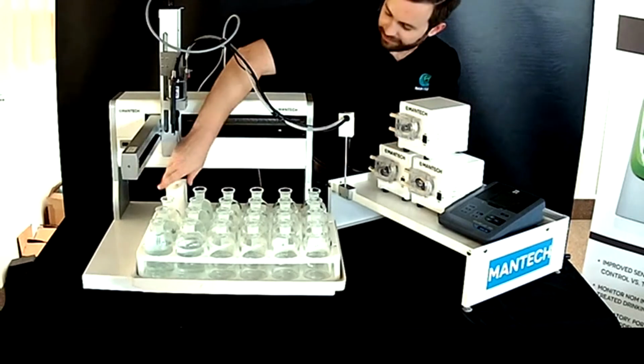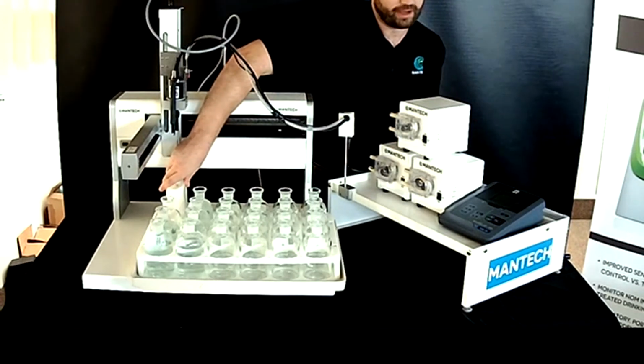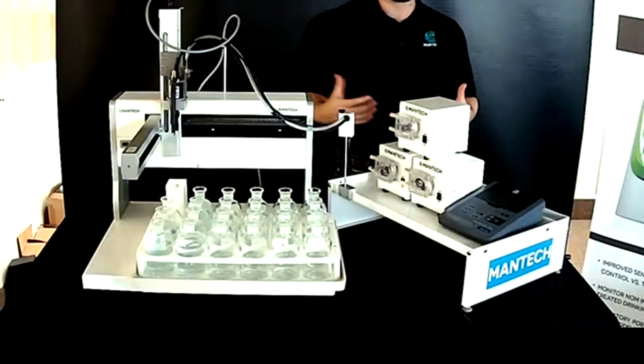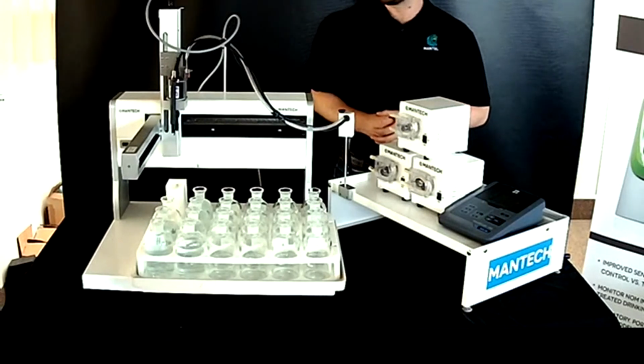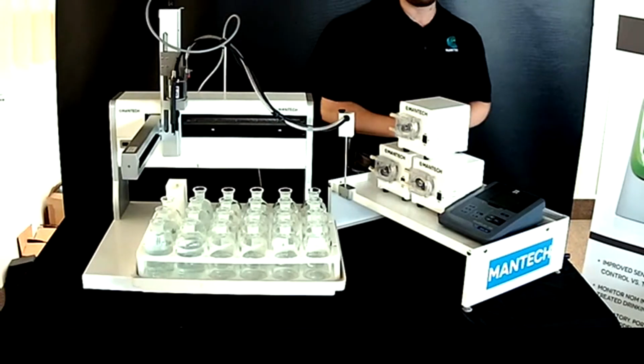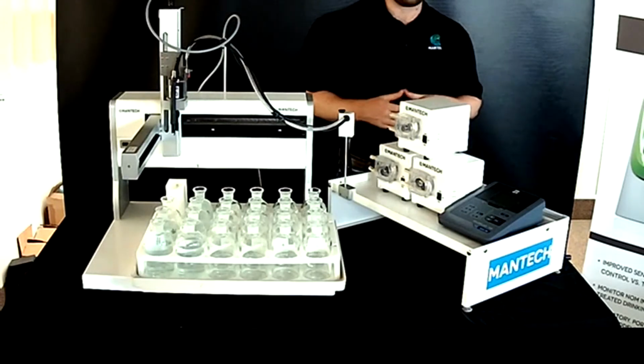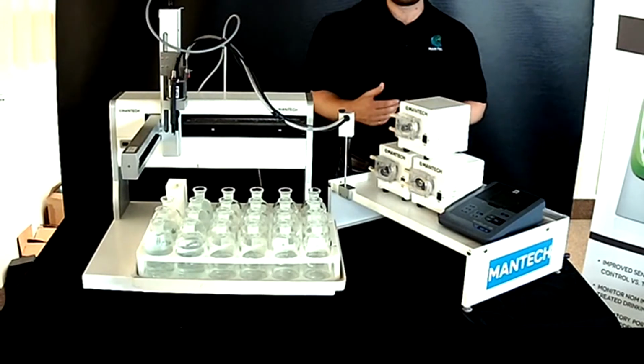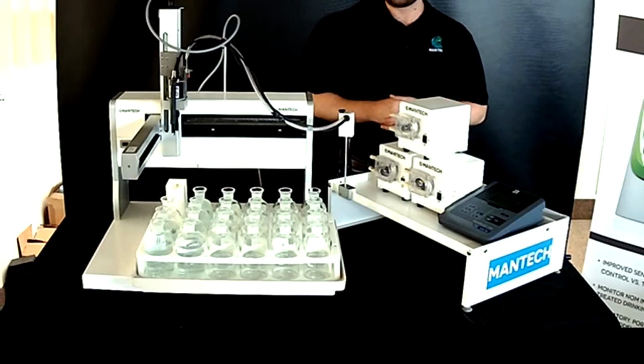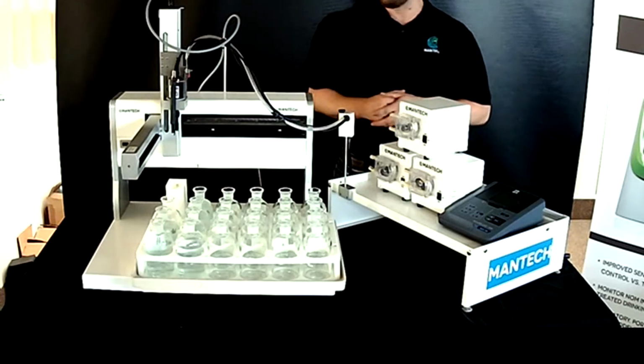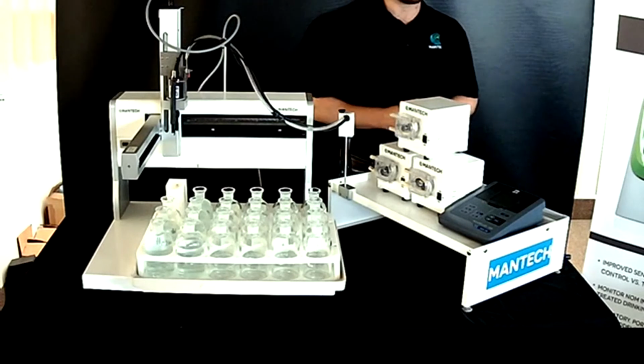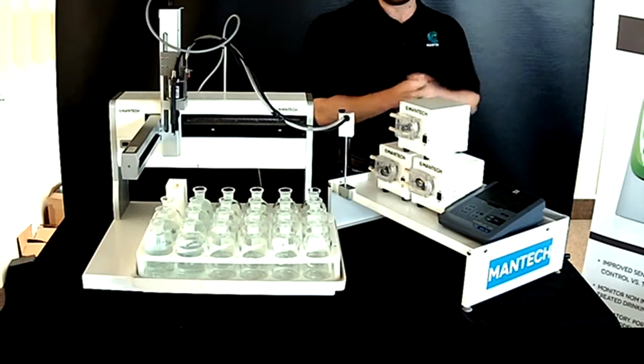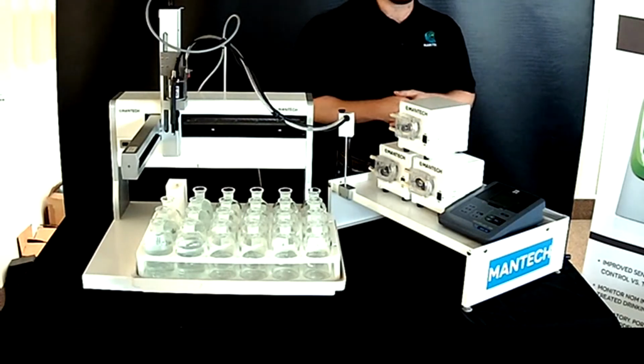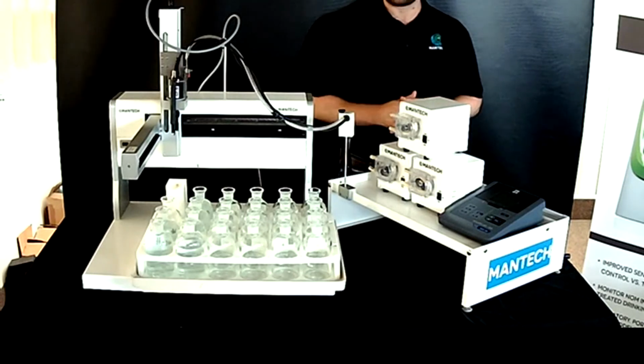And it goes back to this flowing rinse station right here in the back corner, which has flowing rinse water going through it, making sure that those probes are nice and clean, ready for the next sample. We do have an option, if you're running a series of dilutions, to skip the rinsing, because it's sometimes not necessary depending on the sample. But it's pretty versatile software. It's similar to the PeCOD. Well, it's all MANTECH software, right? So we built it the same way.